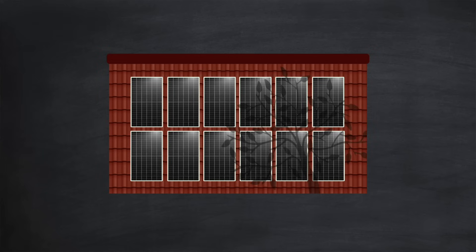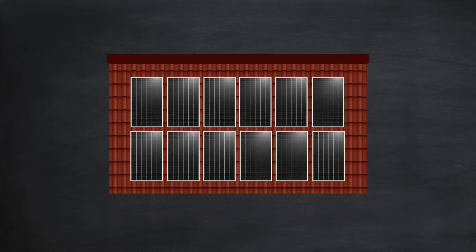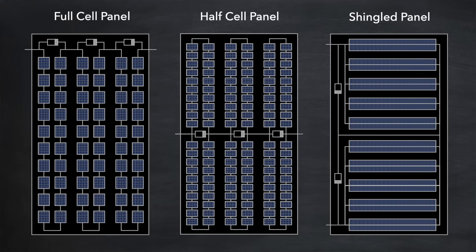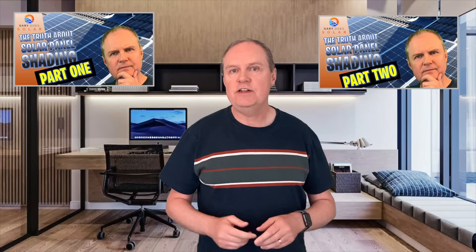So as we've seen, for certain types of partial shading like diffuse shading from a tree, optimizers can marginally improve your array performance. Optimizers can also improve performance if your array experiences shading from a TV antenna or a service cable. But for hard shading, you're likely to find that optimizers perform little or no better than the solar panels can do themselves using their bypass diodes — and this is especially true if your panels are half-celled or shingled. If you'd like to find out more about how optimizers handle shading, I've made a two-part mini-series on the topic — the links are in the video description.